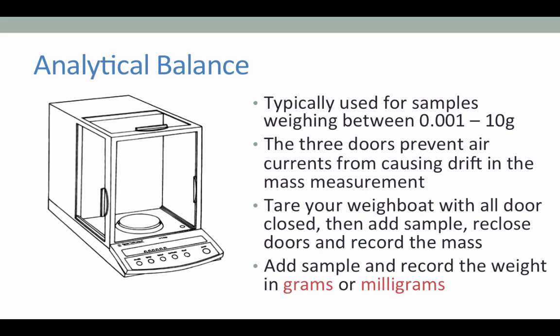The analytical balance, on the other hand, is typically used for smaller samples that weigh between 0.001 and 10 grams. This is because an analytical balance will display a mass down to 0.0001 grams, or one-tenth of a milligram. You will note that an analytical balance has three sliding glass doors. These doors prevent any air currents or small drafts from causing a drift in the mass measurement. It's important that these doors are closed both when zeroing or taring the instrument and when weighing your sample.